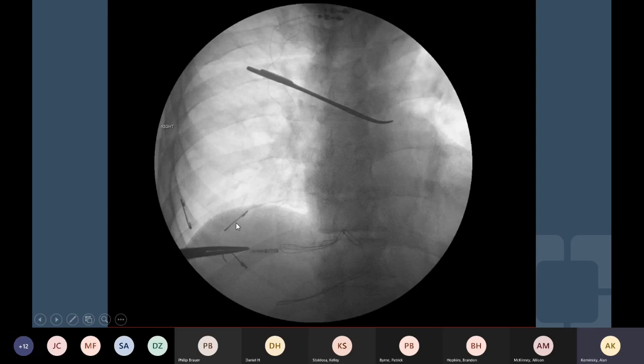But it was then decided that the sensing lead, there was a problem. So when I went back to pull the sensing lead out, the end of the sensing lead was missing. So I was looking at just bare wire. So I had to go and fish between his ribs to find this. This is the metal end of the sensing lead that I showed you before. It's probably about 2 centimeters long.